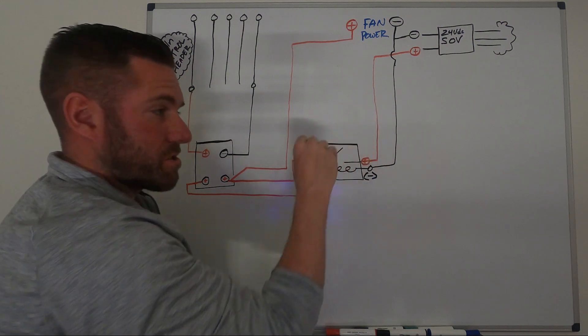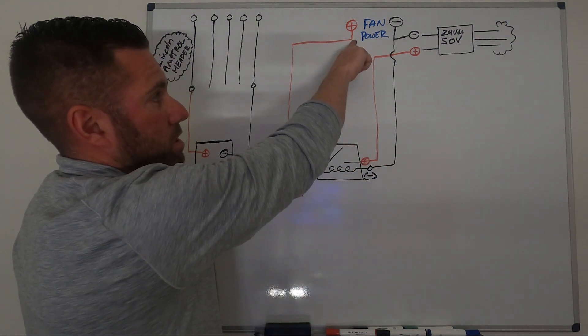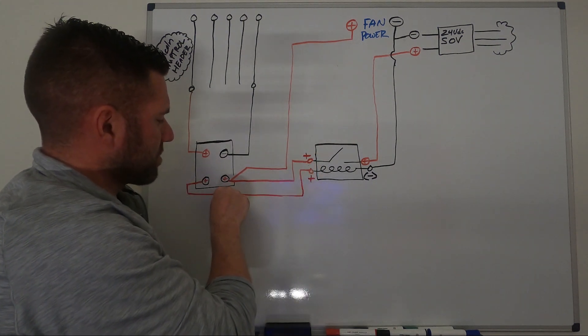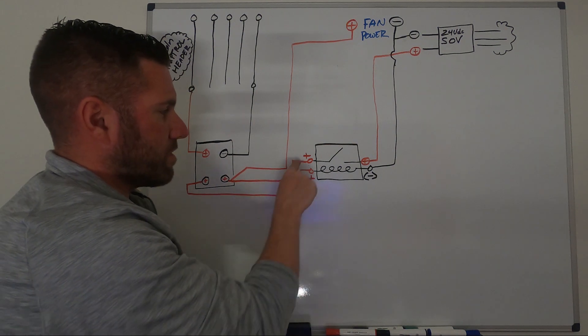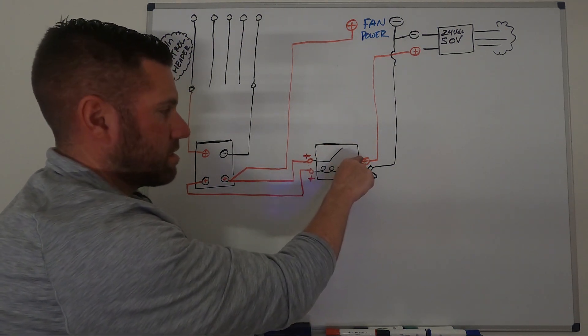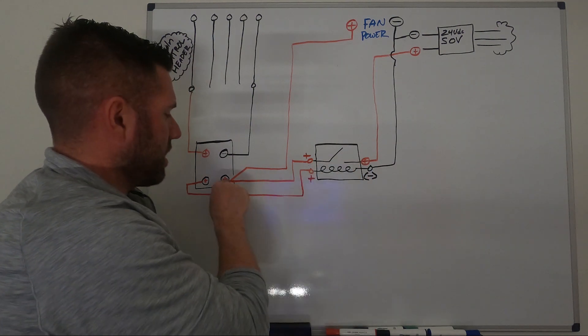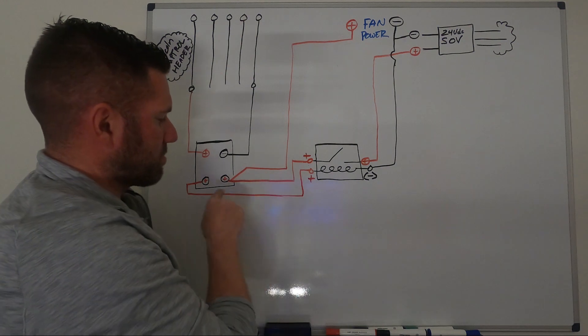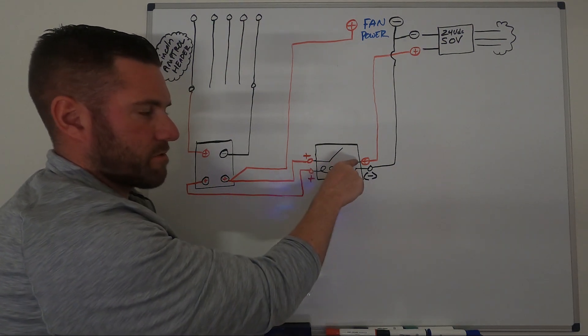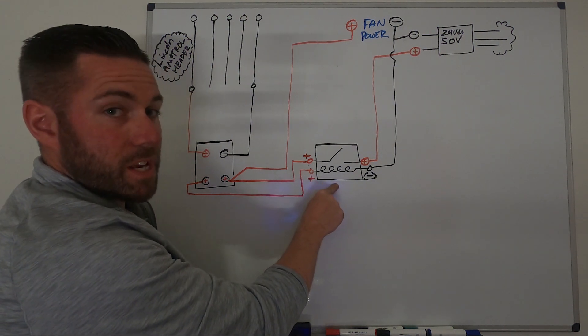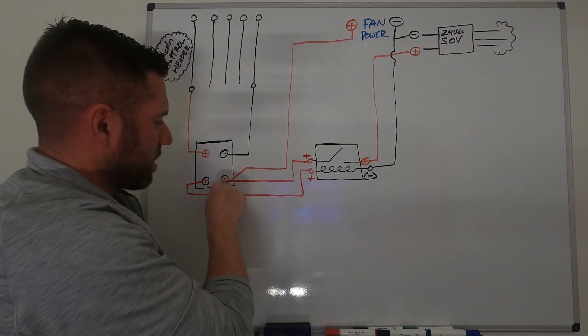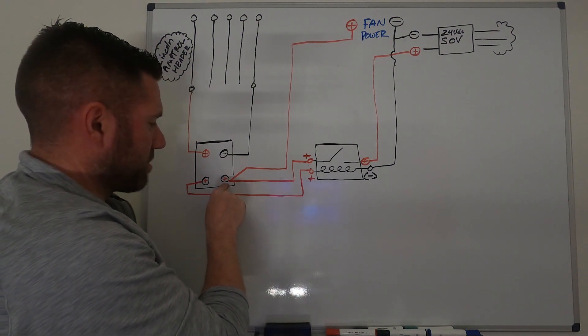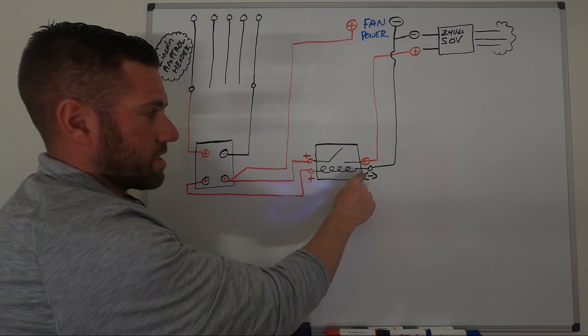We run a positive out, it comes out, goes to the first contact of the relay. Then you'll have two wires here: one will feed the timer relay for the contacts and one will go back to the fan power. Fan power comes down here and the same terminal is the contact for the relay. You don't want to use this same terminal to power this relay because then the gas is always on. We come down here and break off two different wires: one to feed through and kick the solenoid on inside the timer relay, which closes the contact and gas starts flowing.